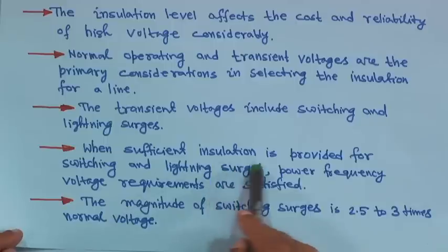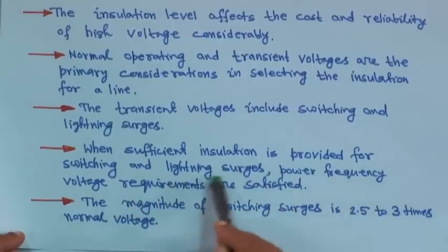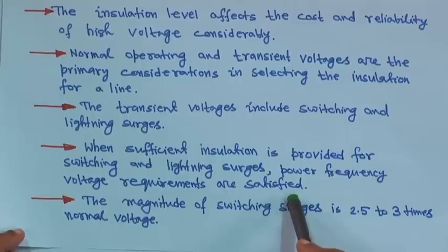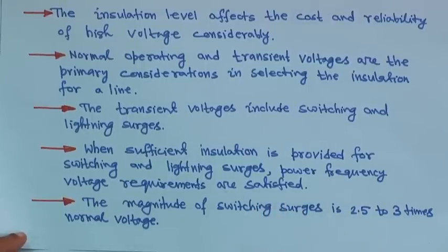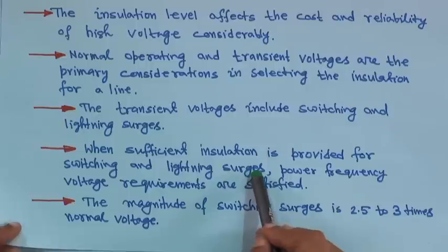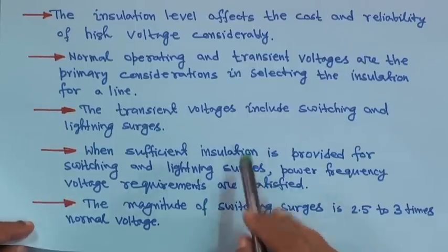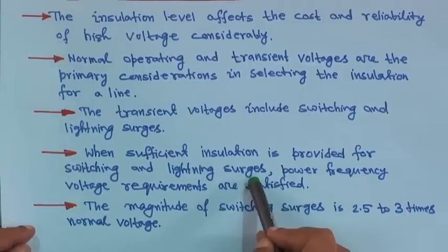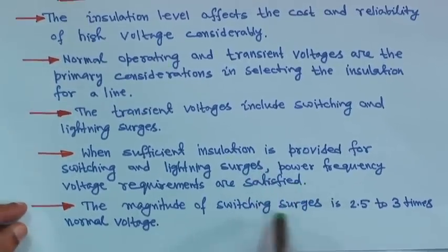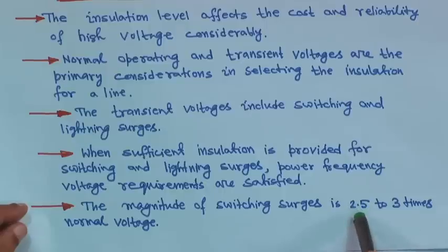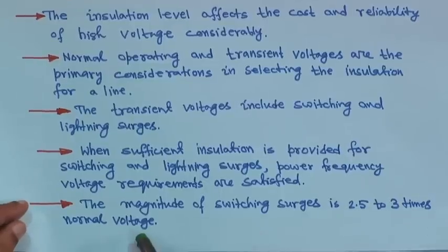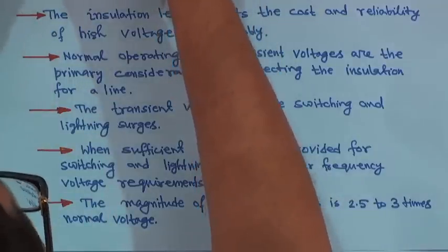When sufficient insulation is provided for switching and lightning surges, power frequency voltage requirements are satisfied. Sufficient insulation will be provided, but switching and lightning surges — particularly when designing — you have to take into account and accurate calculation is required. The magnitude of switching surges is 2.5 to 3 times the normal voltage, so the insulation must sustain that kind of high voltage.